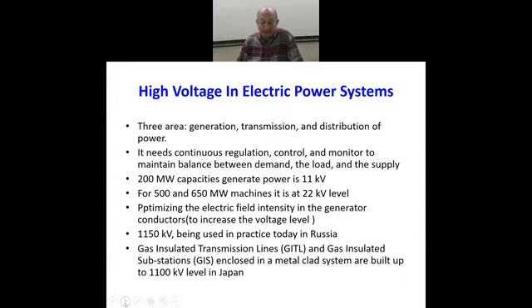And the level of voltage at which this power is produced in the machine, that is the synchronous generator, is at 22 kV only. Then we would like to increase the voltage, but there are constraints in the machine to go for higher voltage. You can imagine when it is 650 megawatt at 22 kV, the magnitude of the current would be very, very large. We'll calculate it, okay?